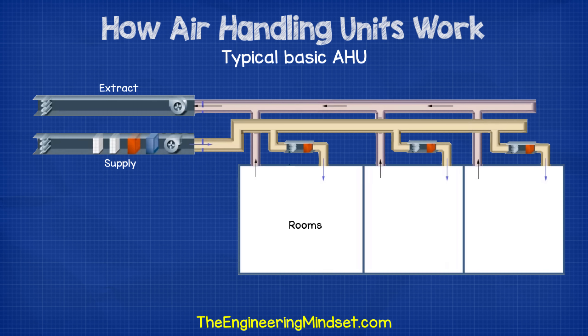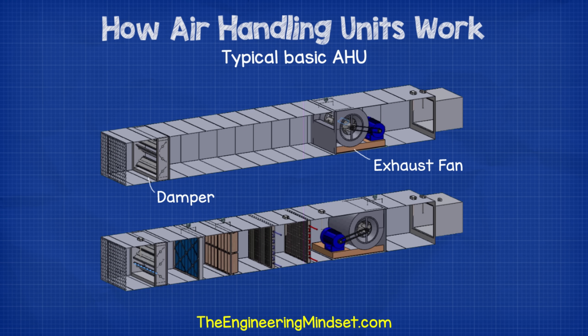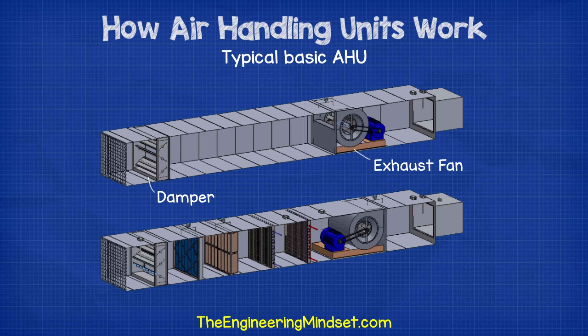Then we have the ductwork which sends the air around the building to the designated areas. We'll also have some ductwork coming back, bringing all the used air from the building back to a separate part of the AHU. This return AHU is usually located near the supply but it doesn't have to be — it can be located elsewhere in the building. The return AHU in its simplest form has just a fan and a damper inside. The fan pulls air in from around the building and pushes it all the way out into the atmosphere, and the damper is located at the exit of the AHU housing and will close when the AHU turns off.